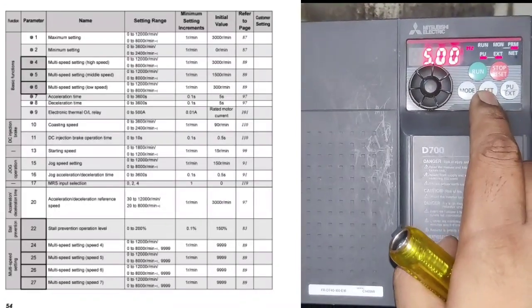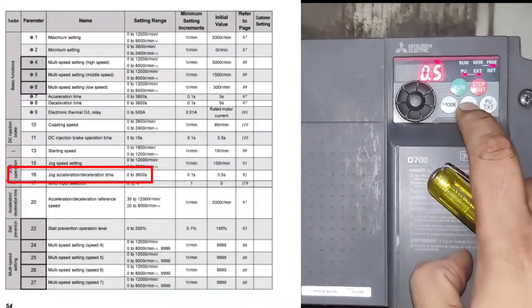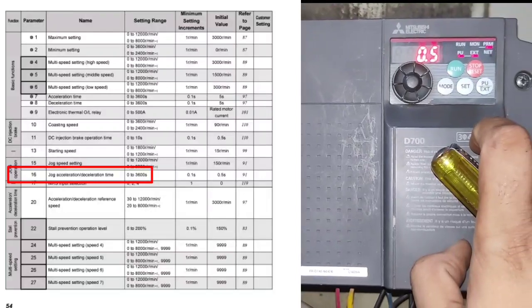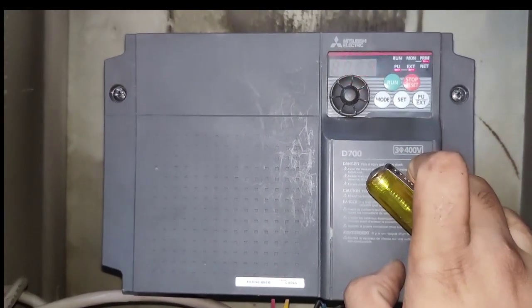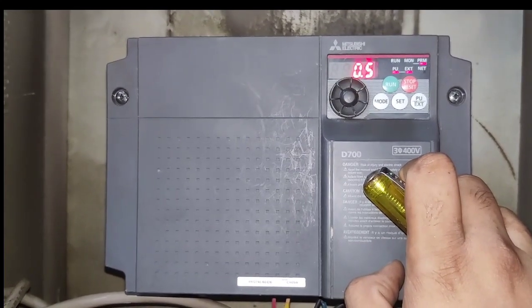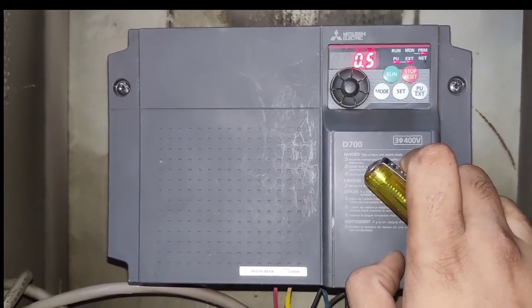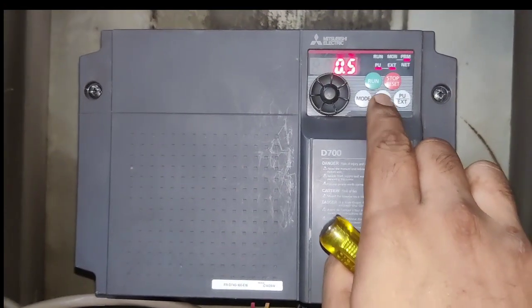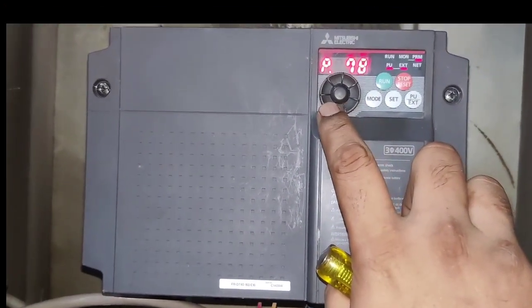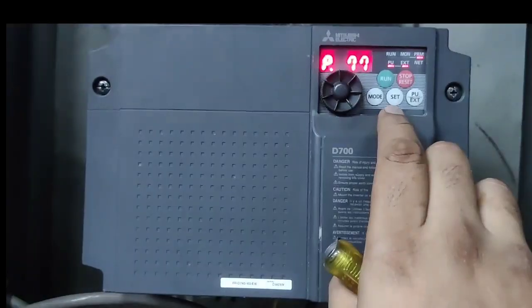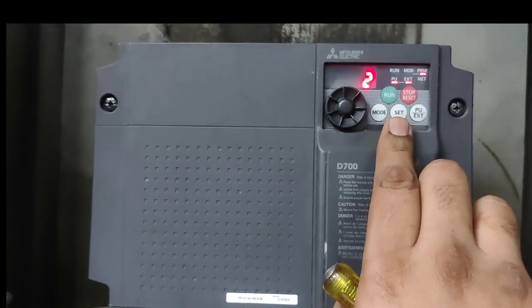Next parameter P16 is for jog acceleration and jog deceleration — that is ramp-up or ramp-down in jog application. For jog acceleration and jog deceleration we set 0.5 seconds.